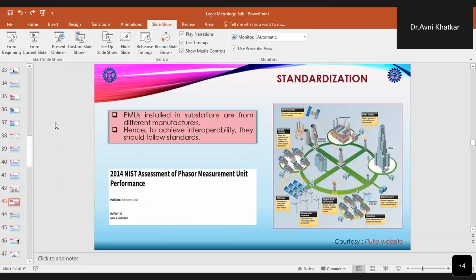Now when we talk about the PMUs, we will have to see their standardization also, how they are standardized. As these PMUs are installed in the grid, in the substations, they are not of the same manufacturer. They are from different manufacturers and they provide data. So in order to achieve interoperability and to have PMUs which follow the standards, this standardization of PMUs came into picture. As they are installed in the utilities, they provide the phasor data. First of all, organizations like NIST develop tests in order to characterize the PMUs and qualify them for the service.